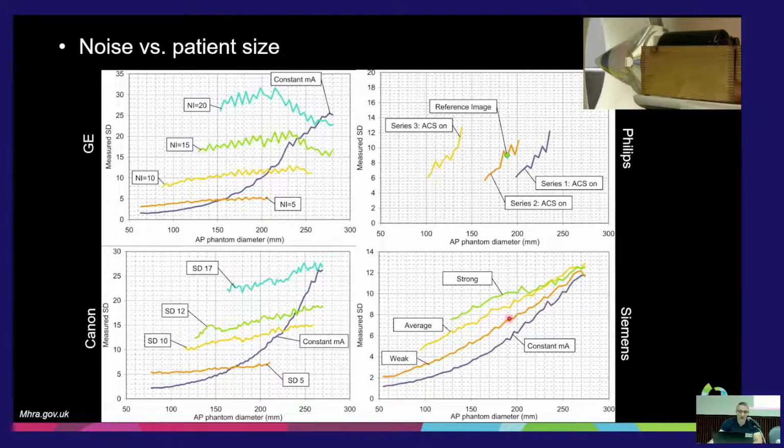It understands the concept that a bigger patient will absorb a lot of those photons, and so a bigger patient can be noisier because they have a lot more adipose tissue. A lot of the anterior part of the body is nothing you're really looking at, and there's a lot of interstitial fat, so there's a lot more inherent contrast in the center part of the body. So it could technically be a little bit noisier. That's the concept that most vendors, except for one, put into their calculations when they set up their profiles, their dose characteristic curves.